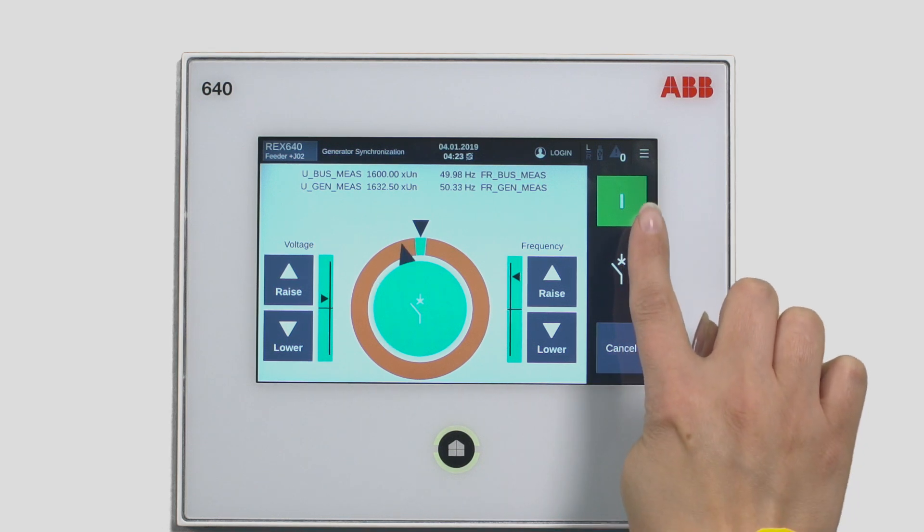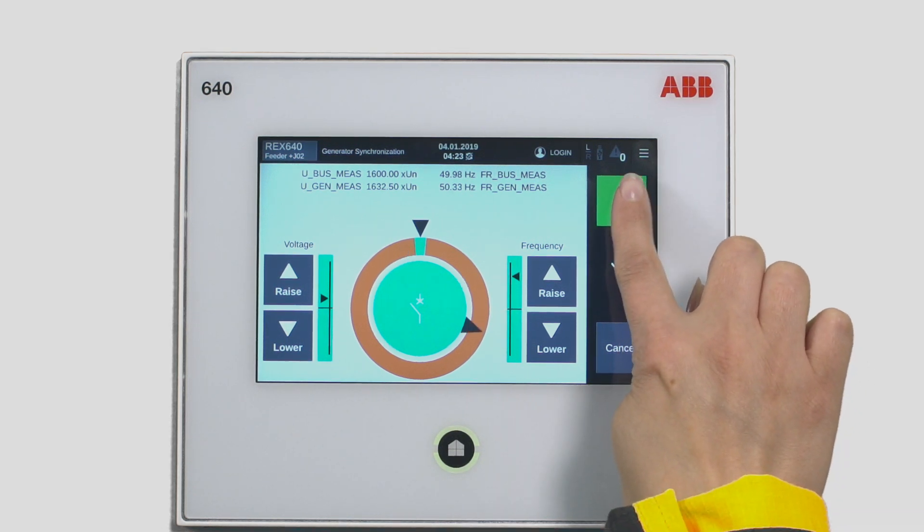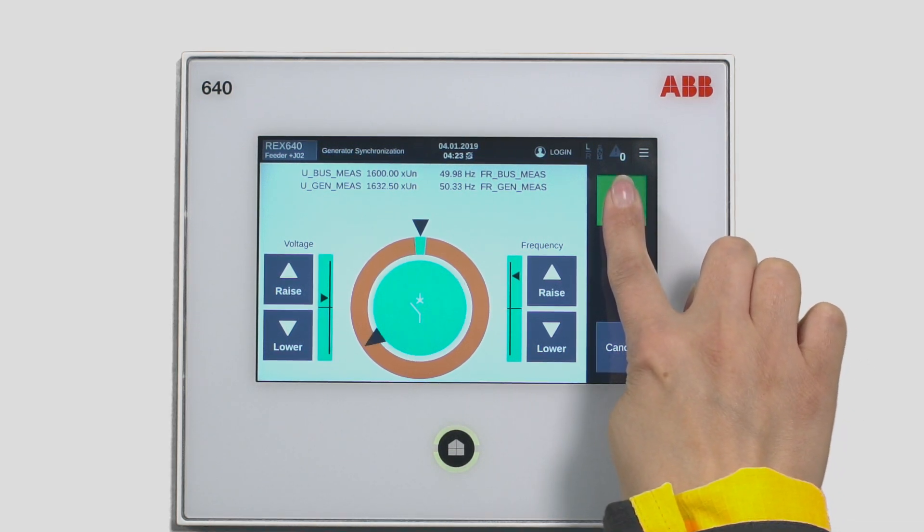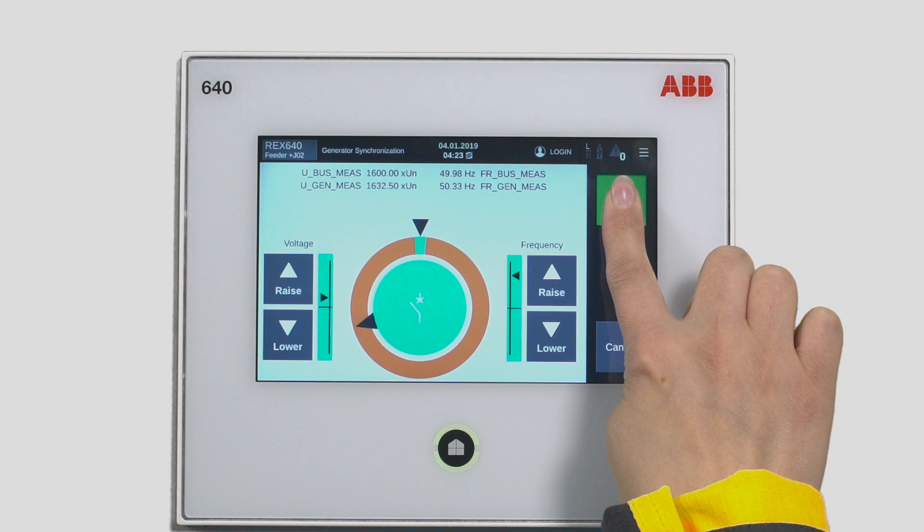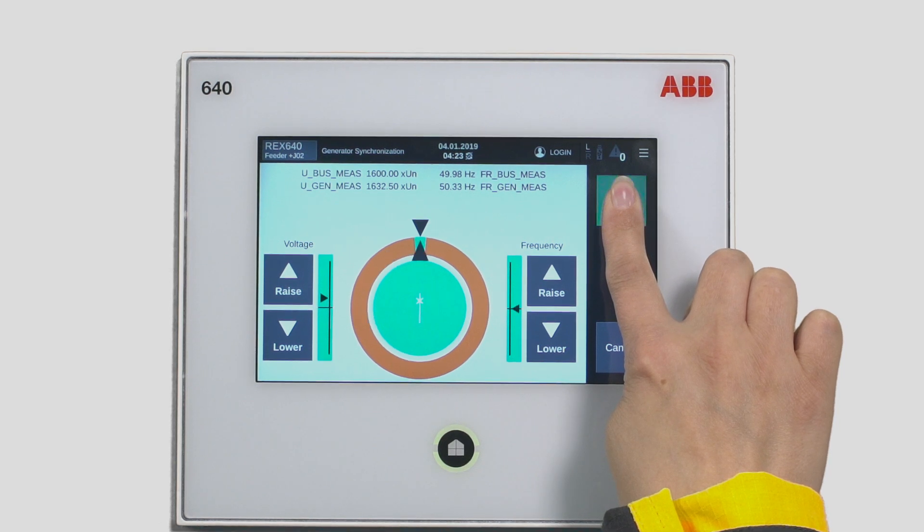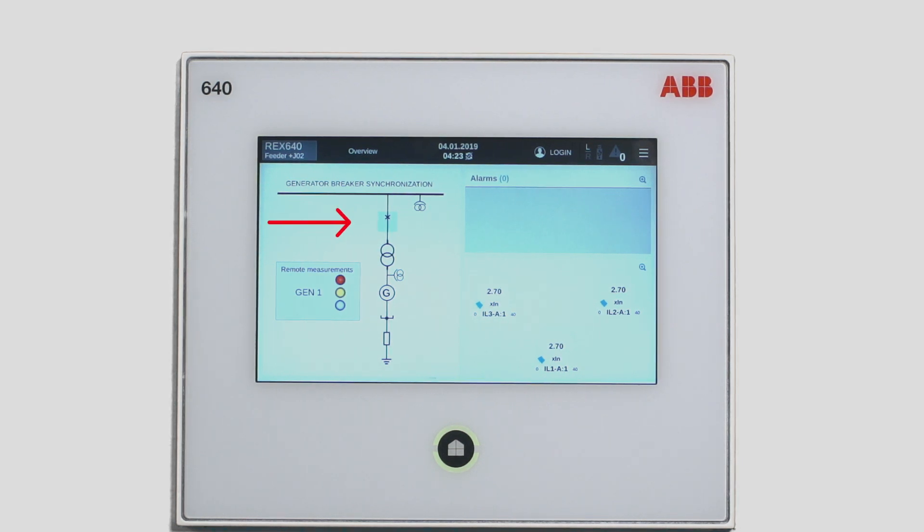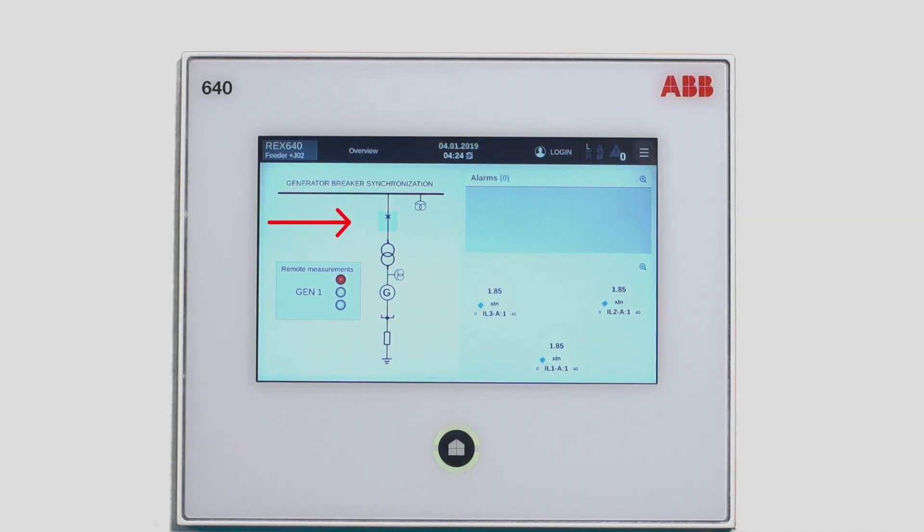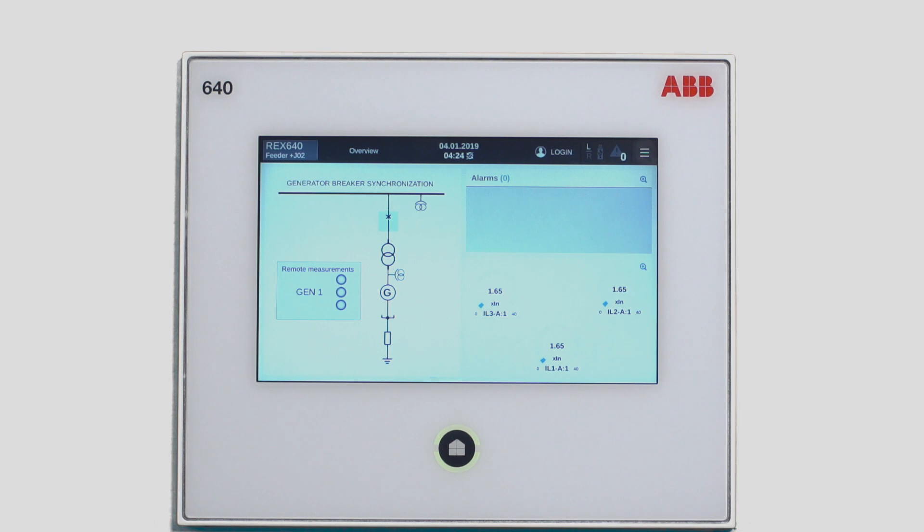Now it looks pretty good. You can start closing the breaker. Tap and hold the close button. When the relay finds the right moment in time, it will send the actual close command to the breaker. The breaker closes as you can see now from the single line diagram.